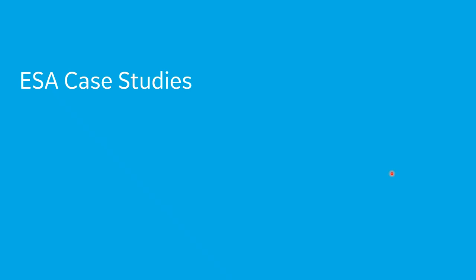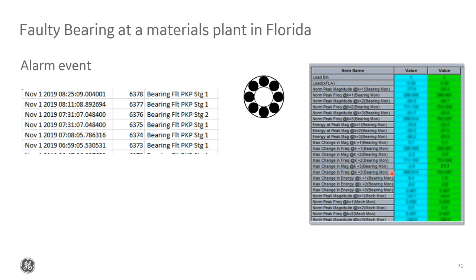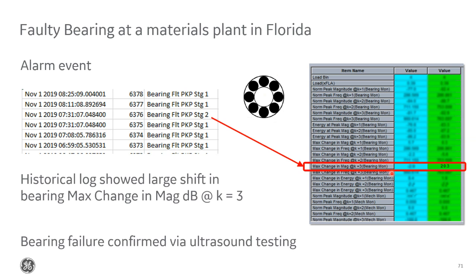And then the last thing I wanted to go over is a few ESA case studies that we have. So I think this was actually Mike's customer. So if you have anything to add, Mike, feel free. But he had a materials plant in Florida in his region that had the ESA option installed on the 869, and it picked up a bearing fault alarm. They said they went out and looked at the motor. Everything looked fine. The bearings looked fine. They don't know what the relay's talking about.